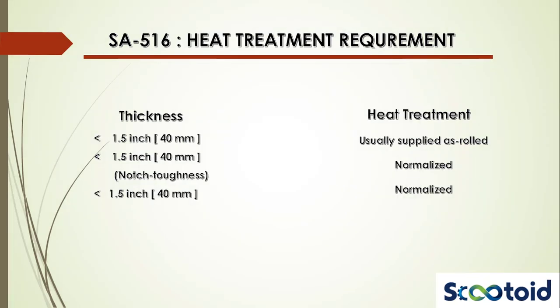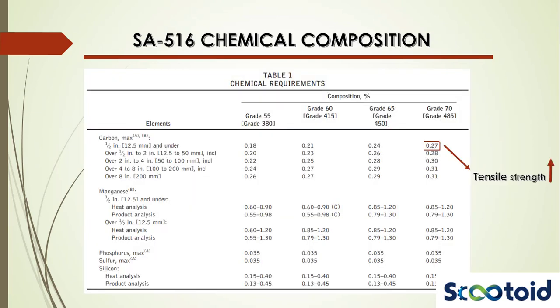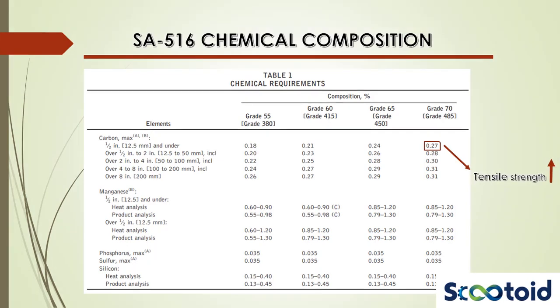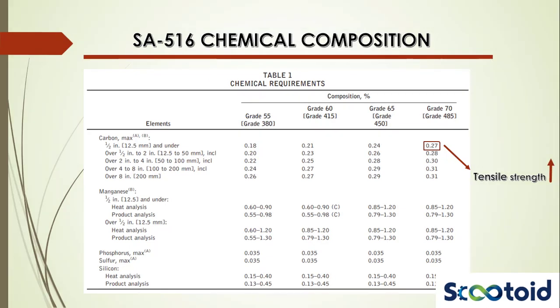Different types of heat treatments are recommended based on the thickness of the plates. Table 1 shows the requirements of the chemical composition of SA 516. For example, for a plate of thickness less than half an inch or 12.5 mm, the most noticeable element is carbon. The maximum amounts of carbon content for different grades range from 0.18% for grade 55 to 0.27% for grade 70. The higher content in grade 70 is the reason for its higher tensile strength compared to grade 55. Other elements included in SA 516 are manganese, phosphorus, sulfur and silicon. The table shows the percentages of these elements for heat analysis and product analysis. Heat analysis is the analysis of the chemical components while the material is in molten condition before it is formed into plate. Product analysis is done after the plate is formed.